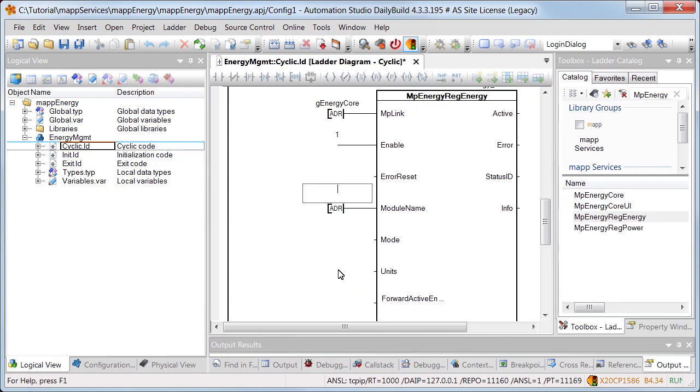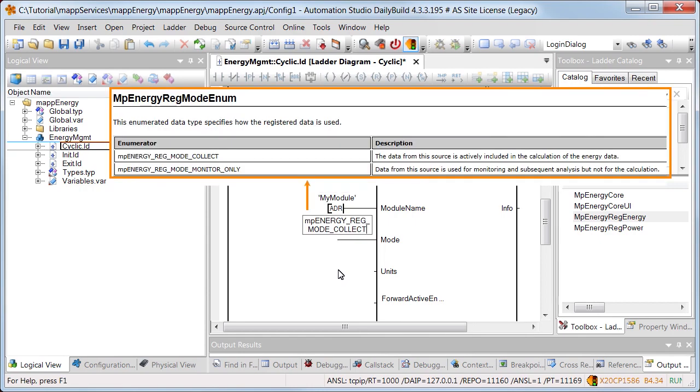The name of the module that provides the energy data is defined using input module name. We'll use the name my module. Mode defines how the registered data is to be used. We'll use the mode MP energy reg mode collect. More information about the mode can be found in Automation Help.